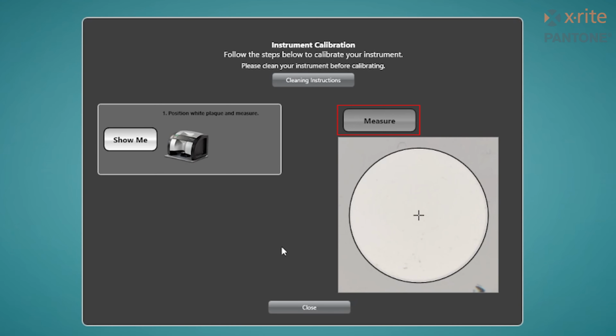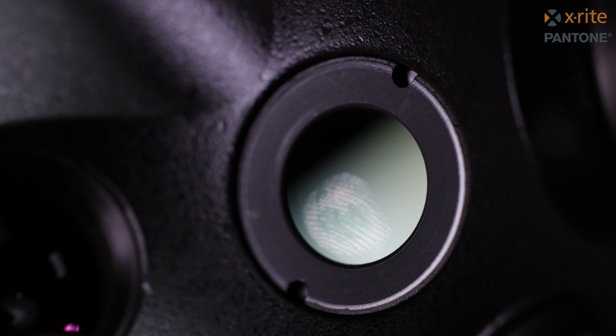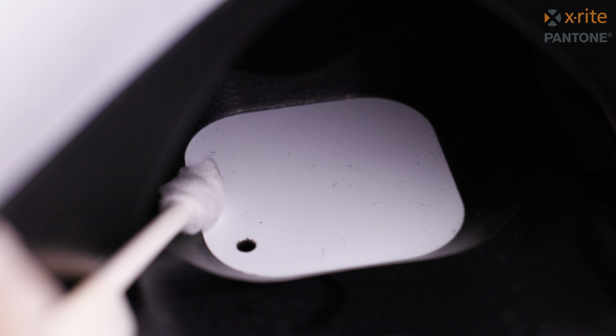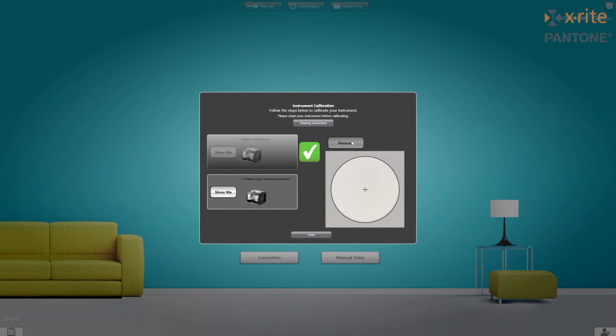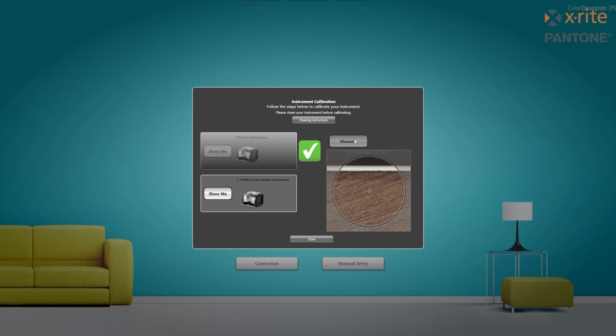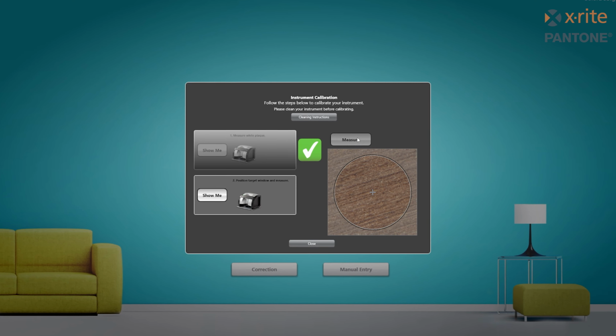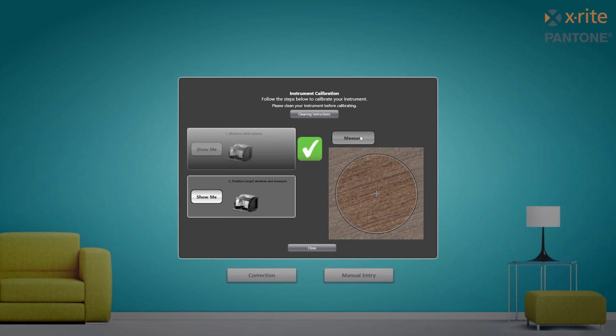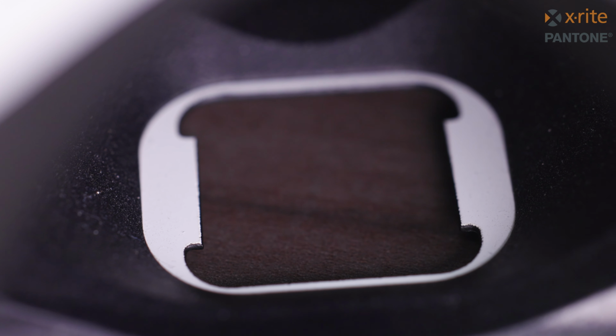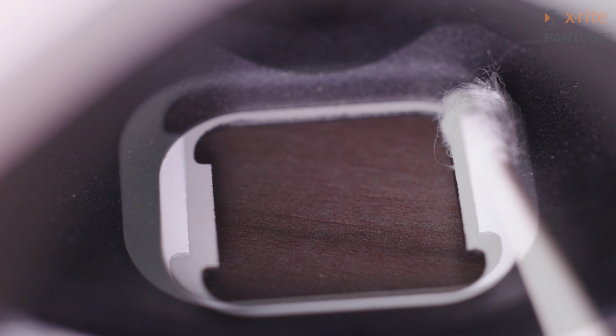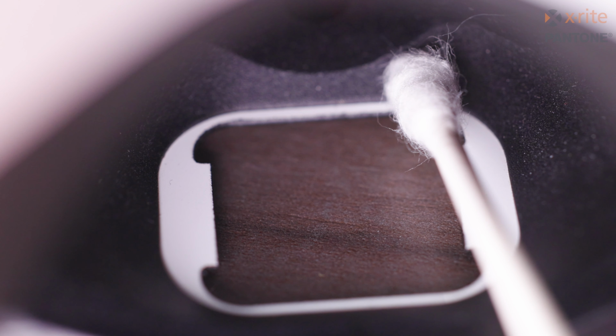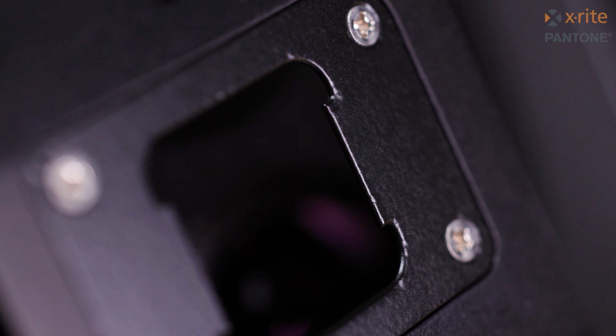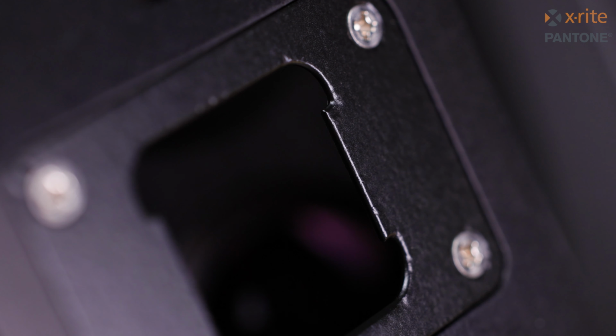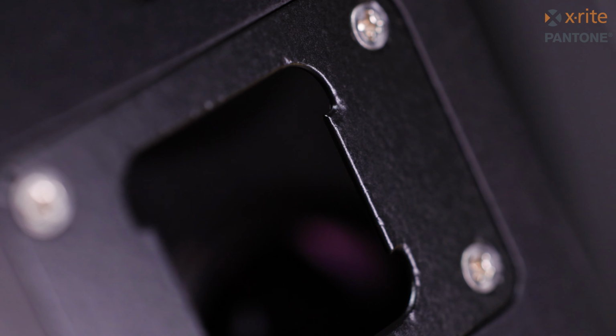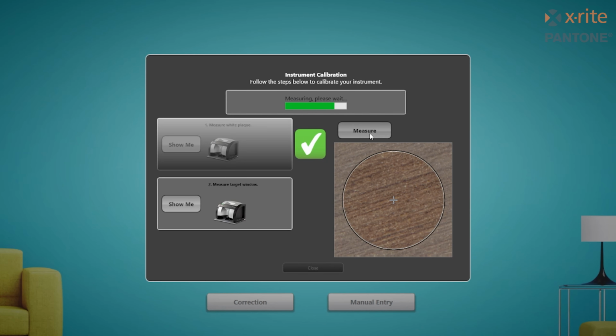If the measure button on the first half of the calibration procedure is still grayed out, check the lenses and white square calibration plaque for contamination. If step 1 of the calibration process completes successfully, but step 2 is grayed out after rotating to the target window position, then inspect that the white tabs on the left and right and small white lip around the outer edge is clean. Also, make sure the sides of the tabs and bottom of the target window are clean. Then attempt to calibrate again.